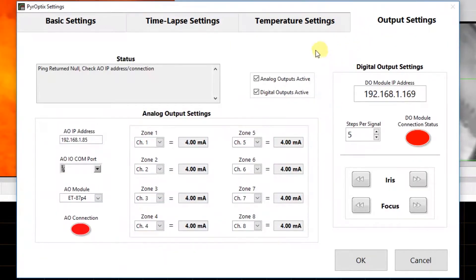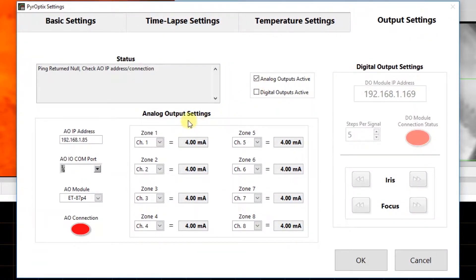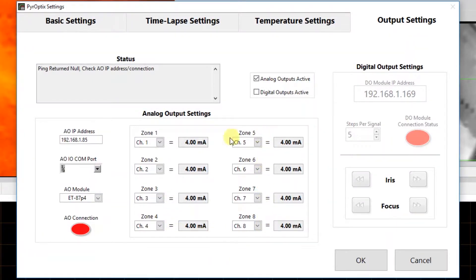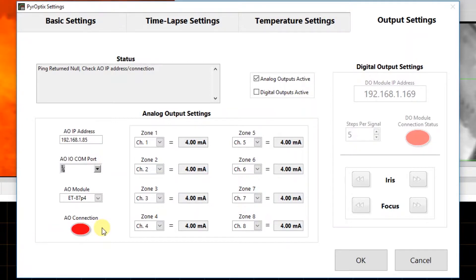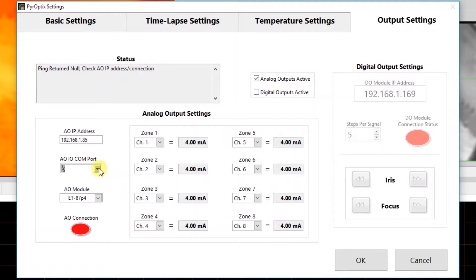Under the output settings tab, we have the option to enable or disable our analog outputs as well as our digital outputs. For our analog outputs, that would be our 4 to 20 milliamp outputs, which does require optional hardware. Under analog output settings, we have our eight zones shown here, and each zone corresponds to a milliamp value — that is the current milliamp output value being sent to the module if it's active. Right now we can see it is not active; the analog output connection shows a red indicator meaning it is not connected, and green would mean that it is. We also have the analog output module, which defines the module we're using, the AOIO COM port, which is the virtual COM port assigned to this, and the AOIP address, which is the IP address of that module.